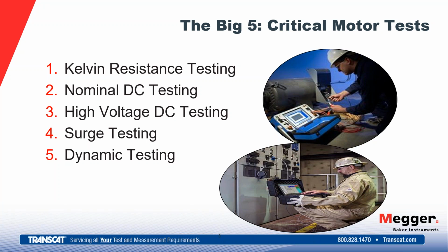And surge testing, the nature of how that test is performed, lends itself to finding turn-to-turn or copper-to-copper insulation issues. So we've tested the ground wall insulation, we've tested our connections with the resistance testing, and with surge testing, we're going to cover turn-to-turn insulation, copper-to-copper insulation.